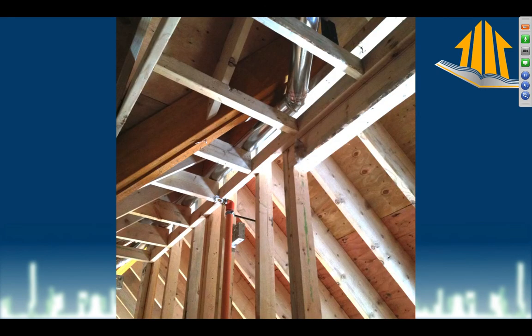This is the mechanical room in the very top of the house, and this is a new thing that people are trying to do where they enclose the mechanical system, the furnace, the air conditioner, in the attic inside of its own insulated and air-sealed room. However, in this case, as in so many cases, we have a wall right here with no top plate. That means that this wall will have air leakage. And what we need to do is make sure that the air inside this wall isn't able to radiate out, because air travels through insulation. So no matter how much insulation we put in here, it's going to be a problem because it's going to be picking up and moving air up through.